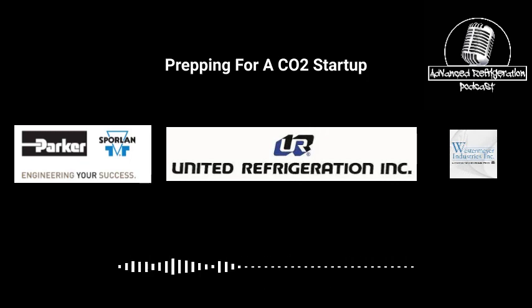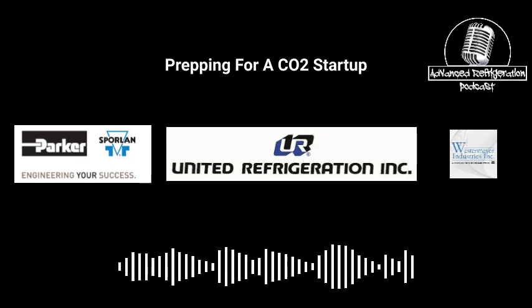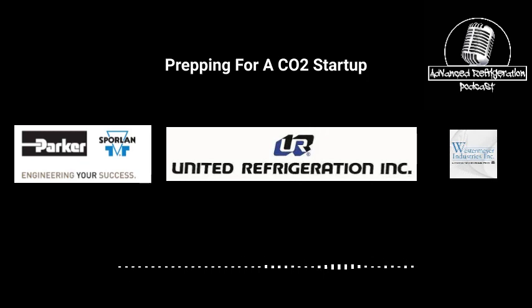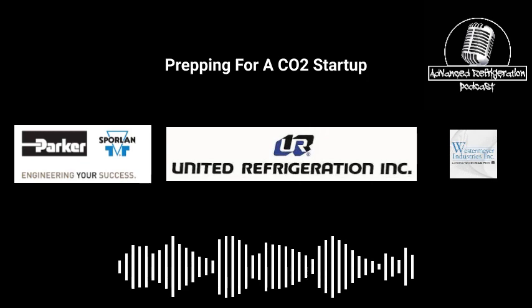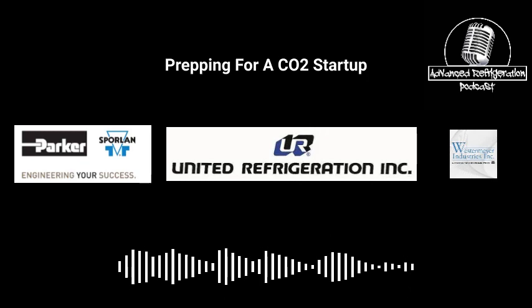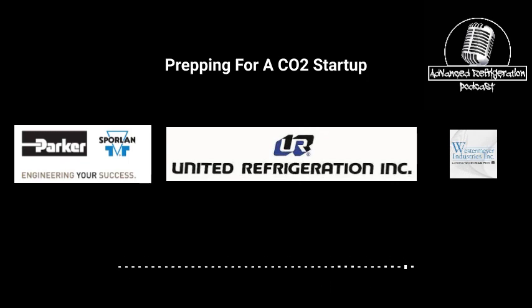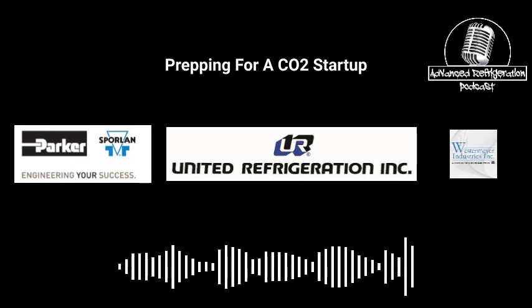So just checking that. I mean, that's a big thing. But back to the rack. You want to make sure on the rack, if you have any check valves or ball valves, make sure they're pointing the right direction. I've been screwed so many times by that, especially liquid to suction, anything like that. Make sure they're pointing the right direction.